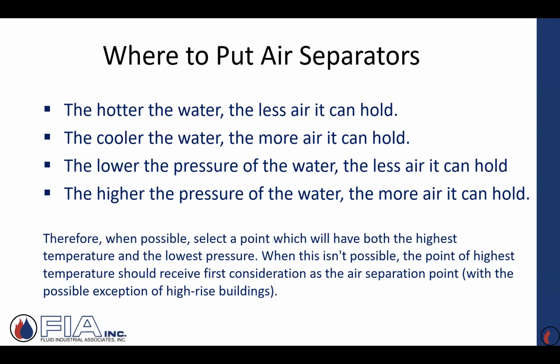One last statement or point of reference, if you will, question comes up, hey, where do I put these? Where do I put an air separator? What's the most logical place? Well, the hotter the water, the less air it can hold. The cooler, the more it can hold. The lower the pressure of the water, the less air it can hold. The higher the pressure, more air is in solution. So therefore, when possible, select a point which will have both the highest temperature and the lowest pressure.